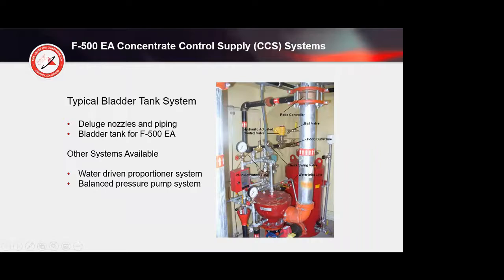So you have your deluge valve that opens up, and here's the bladder tank itself. This is the sight gauge on the bladder tank and a fill line. When we supply these systems, we'll supply the bladder tank with compatible bladders, which is very important because when you deal with a foam system, you deal with a 100% completely UL listed system. So the specific bladder tank is UL listed with the specific foam. The ratio controllers are tested and verified and confirmed with that particular foam, so on and so forth. So since the current encapsulator technology listing criteria for this equipment doesn't exist, we have pulled the applicable parts of UL 162 and run the test.